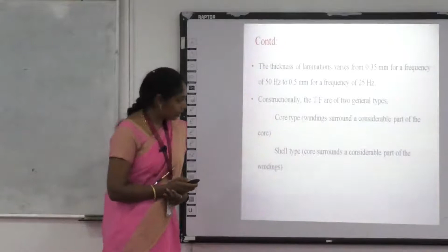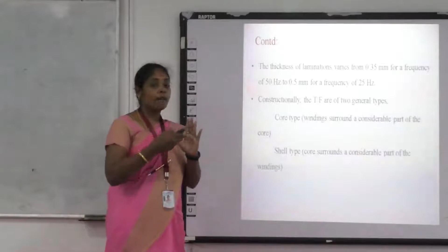Construction-wise, transformers are divided into two types: the core type and the shell type. The core type is where the winding surrounds a considerable part of the core - the core is surrounded by the windings. But in shell type, the core surrounds a considerable part of the winding. That is the difference, and if you understand these two, it is very easy.